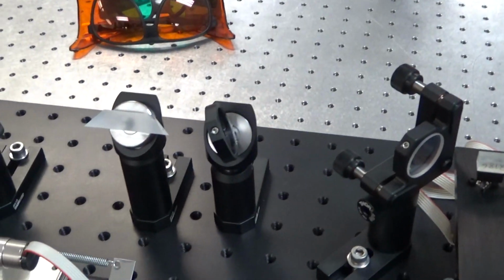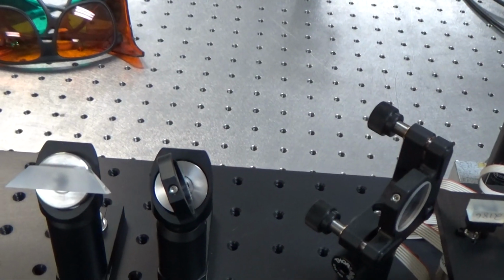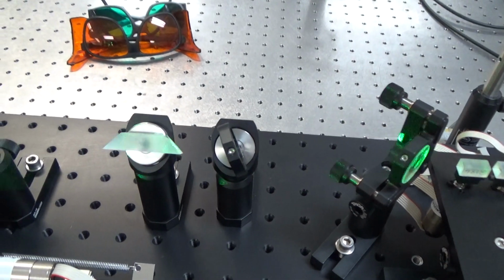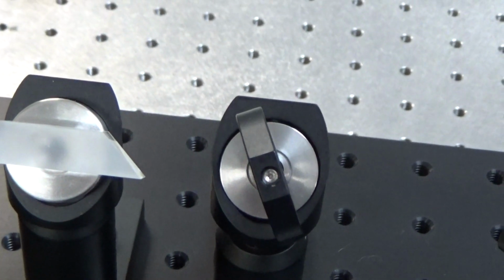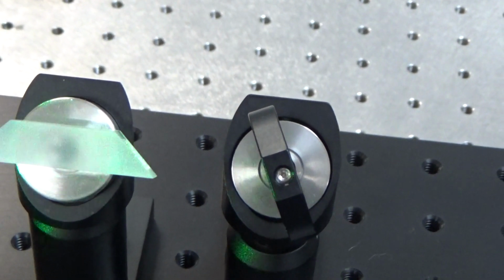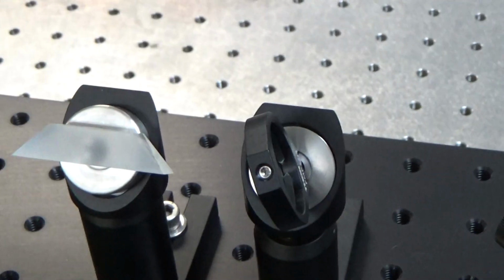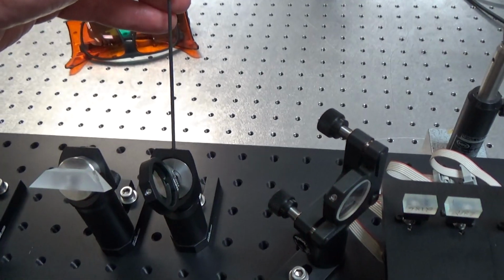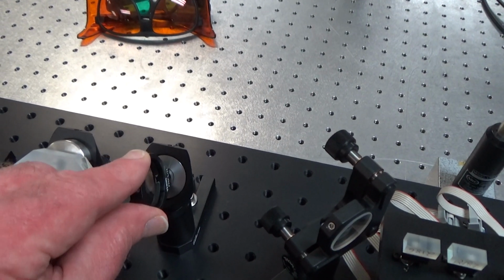Now, what I do to adjust this crystal is simply look at the total energy output from the system with the power meter and optimize the angle as close to normal as possible, but at the first point where the energy is at a maximum. And that's shown at the angle right about here that you'd find at 745 nanometers. Now, to adjust this optic or to remove it, you would simply loosen the set screw and adjust it for maximum energy.